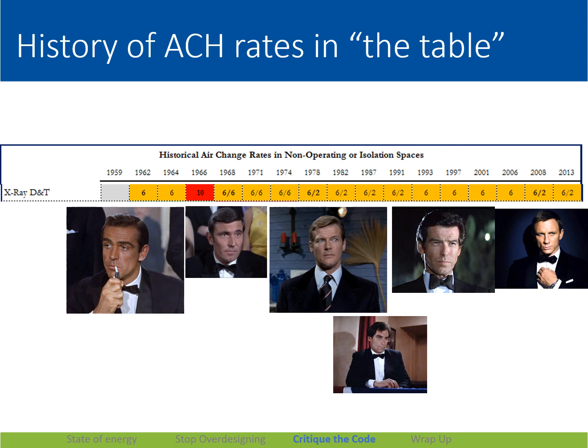Sean Connery is, of course, smoking a cigarette, which was fine in an X-ray room in 1964. We've always used 6 air changes, right? There was one code cycle where it shifted to 10 air changes, kind of like that one movie that has George Lazenby, but then it goes back to 6 air changes. And this is also where I point out that most of the X-ray rooms we've built in the last 30 years are not in hospitals. They're in doctor's offices, which are B occupancy. And in B occupancy buildings, there's no 6 air change requirement. So most of the time that we build an imaging room, we don't use this number. And there's literally no reason to.